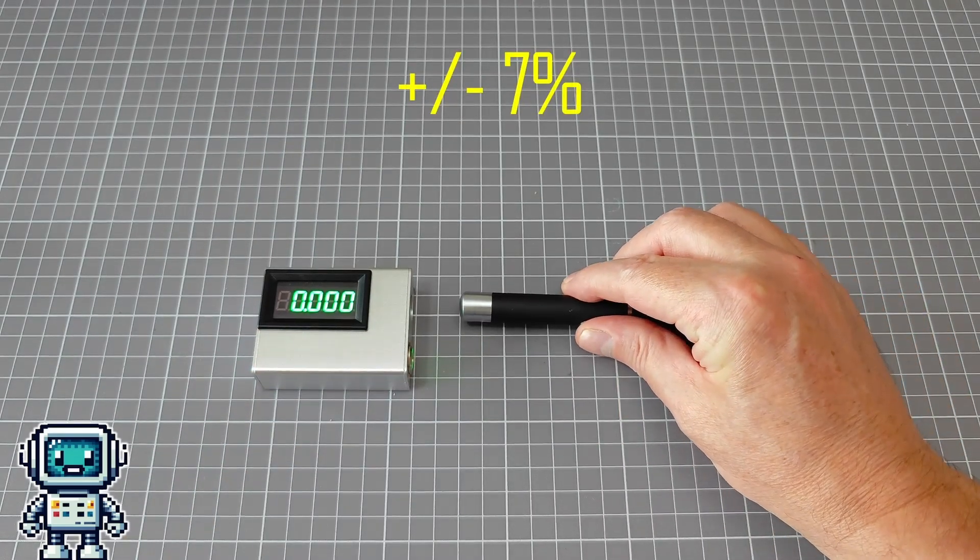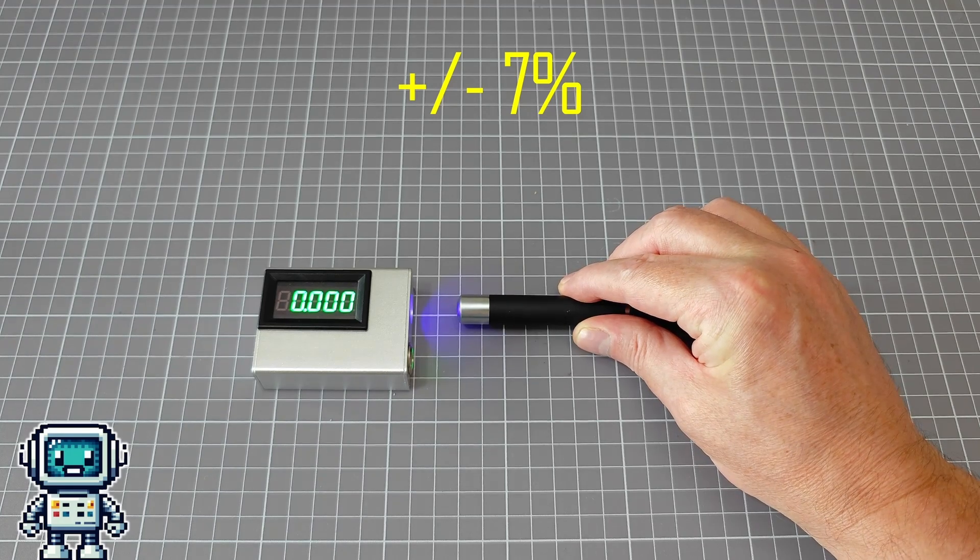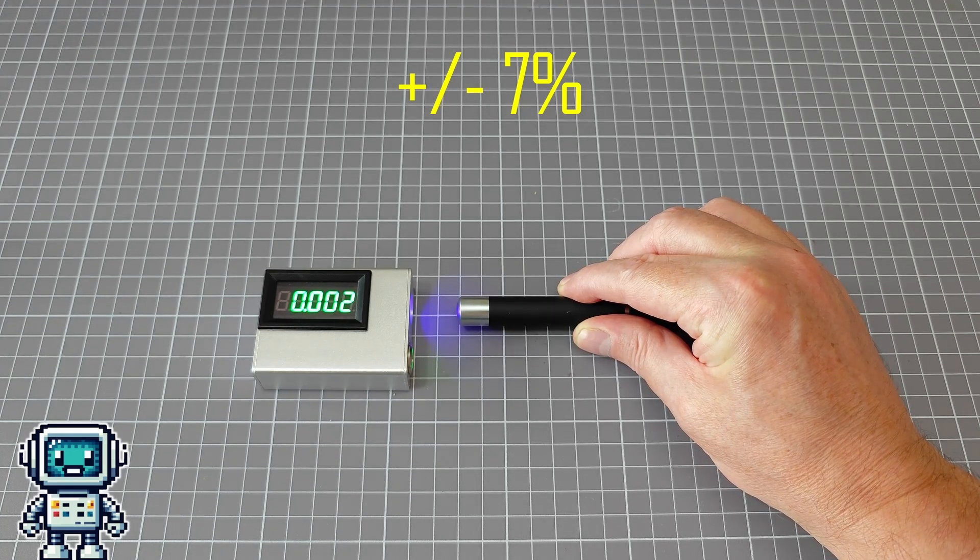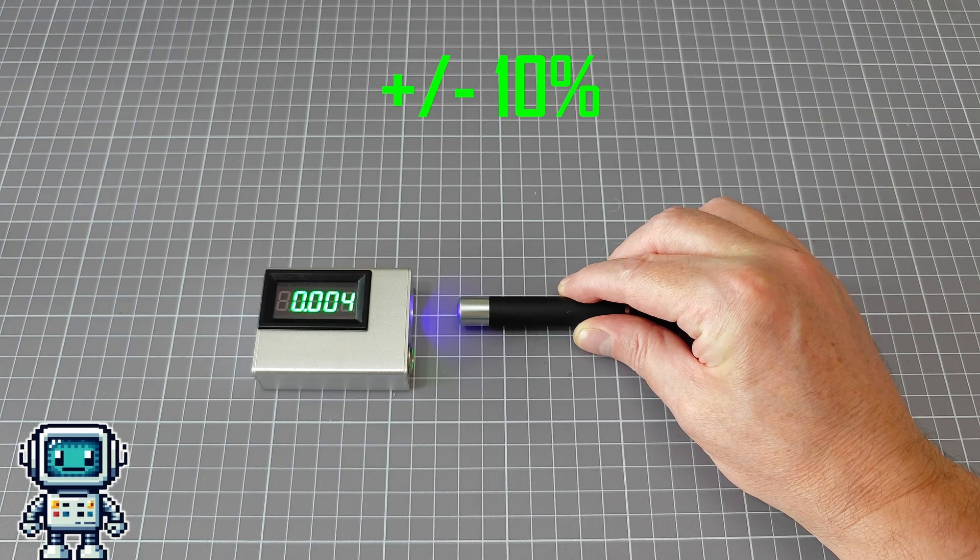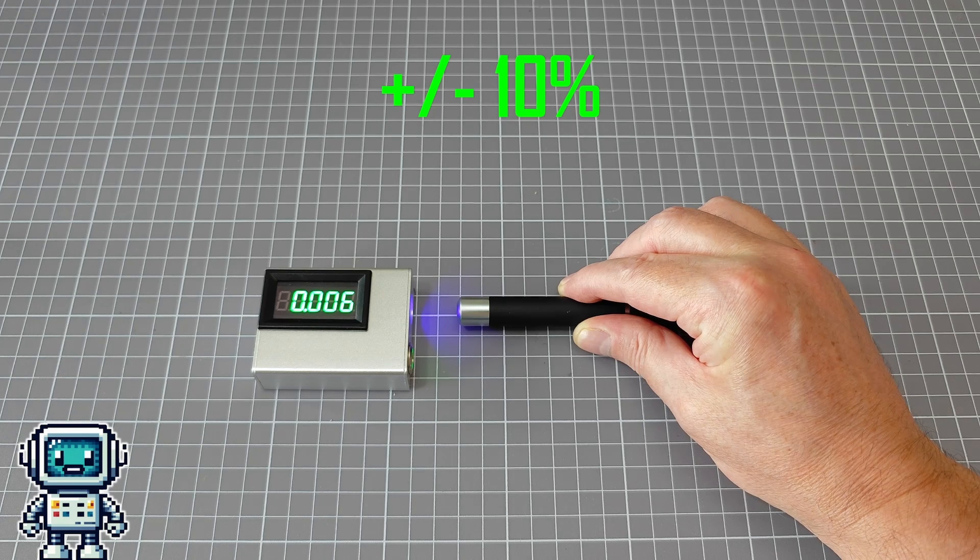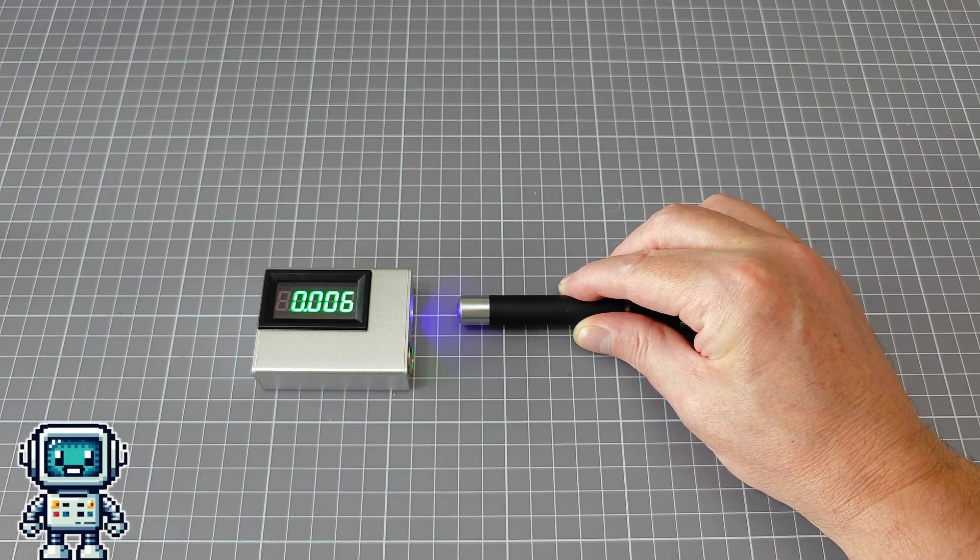If we allow for a tolerance stack up due to errors in the reference power meter, we are probably safe to assume that this is accurate to within about 10%. So whilst this is certainly no precision instrument and it is nowhere near as accurate as the 2% that it claims, it can still be a very useful device.